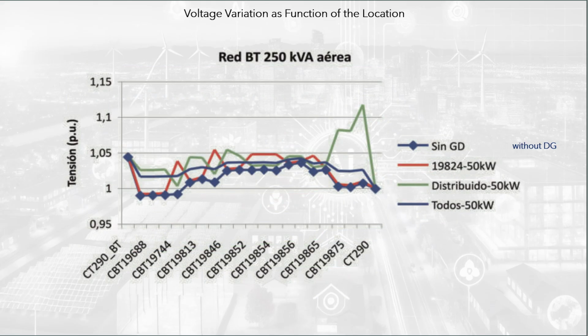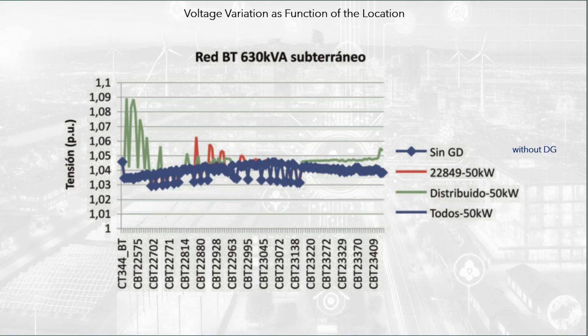The figure shows the voltage variation depending on the location of the DG. The impact of the 50 kW injection has been analyzed. 3 locations of this injection have been studied: concentrated in an end-of-line node, distributed in 5 nodes that are end-of-line, and distribution of the injected power among all the nodes of the system. On the other hand, the more the active injection is distributed in the grid, the lower the impact on voltages and therefore the lower the probability of overvoltages. This is the situation that could be expected in the future, where different PV units are installed on a DG basis.